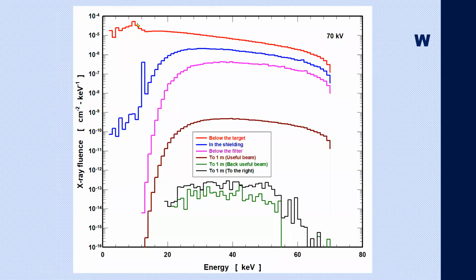The results that we obtained from this work, I'm going to present here: all the spectra when we use an X-ray tube working at 70,000 volts, having a tungsten target. We can notice that just below the focal point, inside the glass, we have this spectrum that contains the larger amount of photons, with a large contribution due to the low energy photons. When this spectrum passes through the glass, the spectrum changes from red to blue, and we can notice a reduction of the amount of photons, and the largest reduction is noticed in the low energy photons.